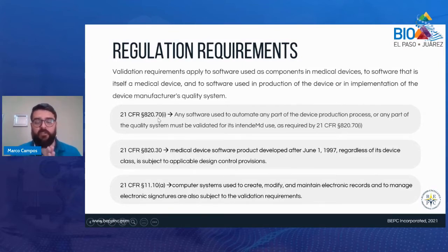820.70 is a regulation that says if you're going to have software in your device, it needs to be validated. 820.30 says the medical device software needs to follow design control, which is another topic by itself. And again, 21 CFR 11 - if you have any software used to create, modify, or maintain electronic records, it also needs to be subjected to validation. So regulations for software are very robust, very similar to what you would see for product or process. If you're looking into implementing a technology like this, you will really have to do your homework to make sure the validation meets the regulation.